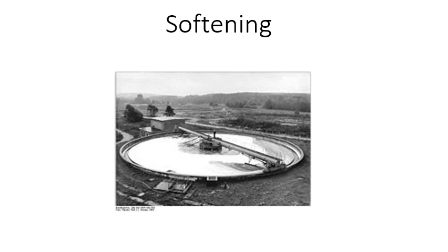So here's an example. If you have a total alkalinity of 250 milligrams per liter of calcium carbonate and a total hardness of 100 milligrams per liter of calcium carbonate, the total alkalinity is greater than total hardness, therefore all hardness is carbonate hardness, temporary hardness.